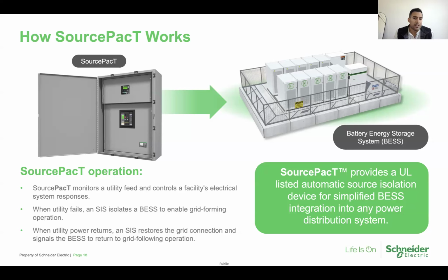Once we decide to reconnect back to utility, we'll send a shutdown signal to the inverters in the battery energy storage system, telling them to shut down. That motorized breaker will close once again, and then the inverters sense that there's an available anchor resource and synchronize to that source.